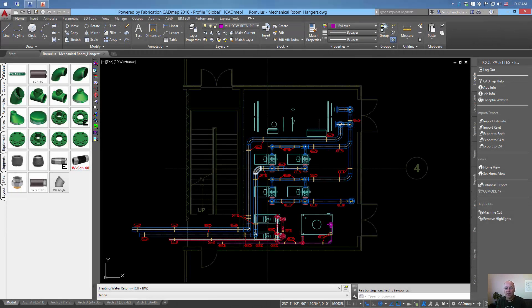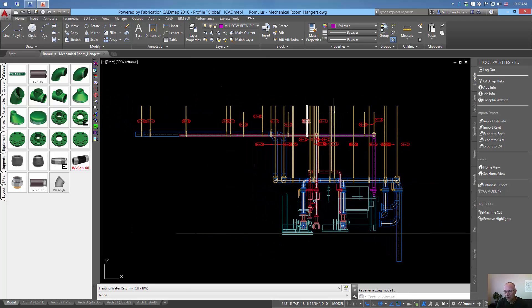Hello, today I want to show you a trick for dealing with hangers on a sloped roof. In the past this has just not been possible with CAD MEP, but with CAD MEP 2016 and Revit 2016 we can get it done. I'll walk you through the steps. Here I have a small mechanical room with some hangers that I'm working on. If I go to a front view, we'll see that most of my hangers are all at the same level — but they're at the wrong level because I have a sloped roof in this room.